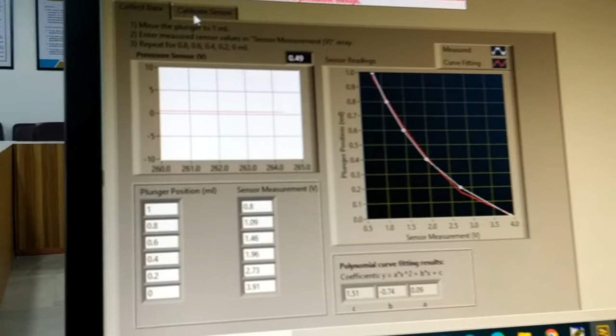So first part of this experiment was to collect the data from the pressure sensor, that is complete now. Second part is to take these readings, the ABC coefficients, and insert them into the calibrate sensor tab. I'm going to copy this A reading and place it in the calibrate tab, in A reading. Then B reading from here, I'll place it in the B column. Third reading is 1.51, I'm going to place it in the C reading.